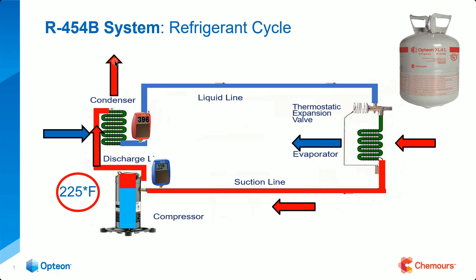Years ago with 10-SEER equipment, there was a rule of thumb that was pretty spot on almost every time. I started when 8-SEER equipment was the new SEER. In 10-SEER equipment, you could almost bet that whatever the condensing saturation temperature was, it was about 30 degrees higher than outside ambient. So if it was 80 degrees outside, you were seeing on your high side about 110 degrees saturation inside the condenser at about midpoint — playing on the second law of thermodynamics.